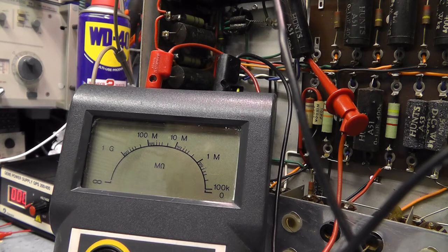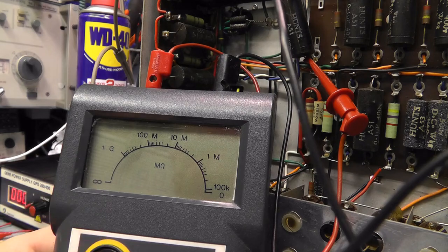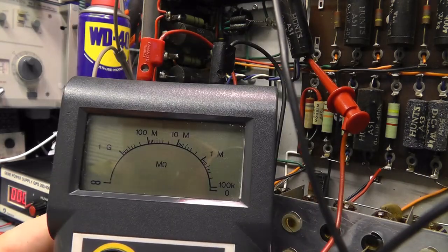So what I'm doing now is applying a DC voltage across this Hunt's capacitor, rated at 400 volts DC. I'm going to apply 250 volts across it, which is what I'm expecting. As everyone should know, when you apply a DC voltage across a capacitor it shouldn't pass any current at all, and if it does, it will show up as a resistance. We're looking at the meter here, and we should see the bar graph swing round to the infinity sign. So let's press the test.